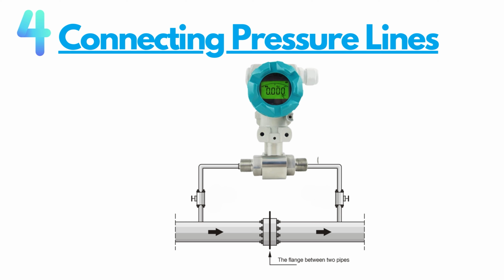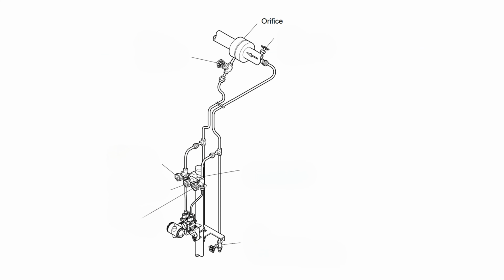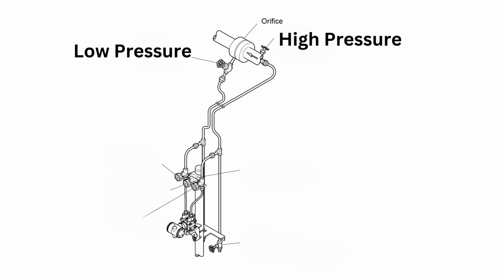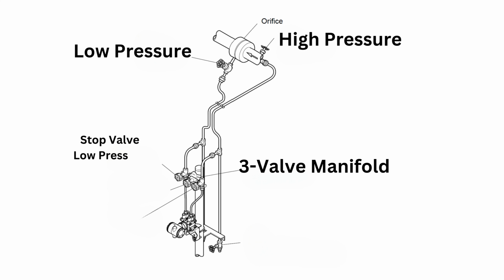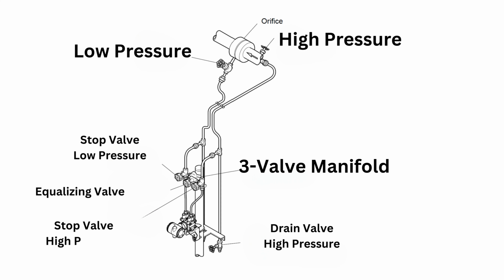Step 4. Connecting the pressure lines. Now, connect the pressure lines. Remember, symbols H and L are shown on a capsule assembly to indicate the high and low pressure side. Connect the high impulse piping to the H side and the low impulse piping to the L side. Connecting the transmitter and 3-valve manifold. A 3-valve manifold consists of 2 stop valves to block process pressure and an equalizing valve to equalize the pressures on the high and low pressure sides of the transmitter. Such a manifold makes it easier to disconnect the transmitter from the impulse piping and is convenient when adjusting the transmitter 0 point.